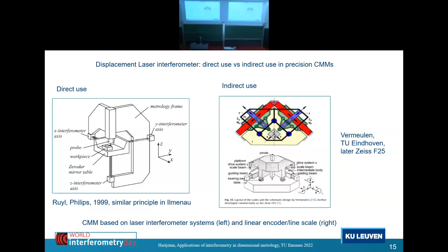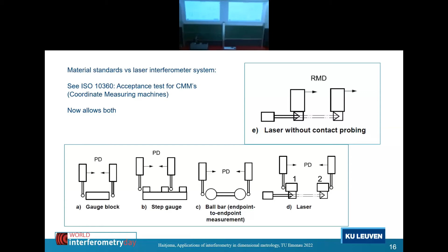And still with those two ways, do we need materials or do we use laser beams? You can still see in some of the ISO standards, if you look at the acceptance test for CMMs, there are in fact two ways. The material way, you use some material, a gauge block or a step gauge or a ball bar, or you use the laser interferometer. These gauge blocks were calibrated before by interferometry. Step gauge, I will show you an example of how that was done. Ball bars are similar, and can also be done by some way of interferometry.